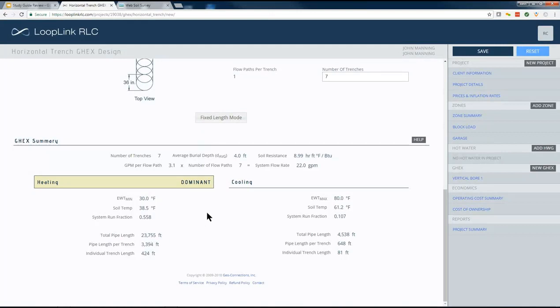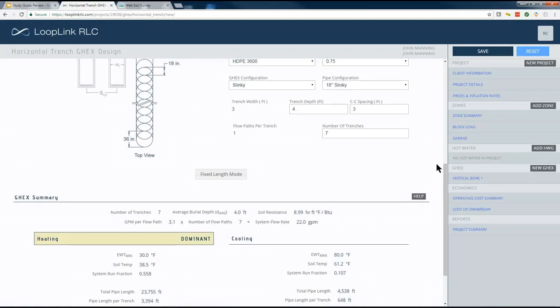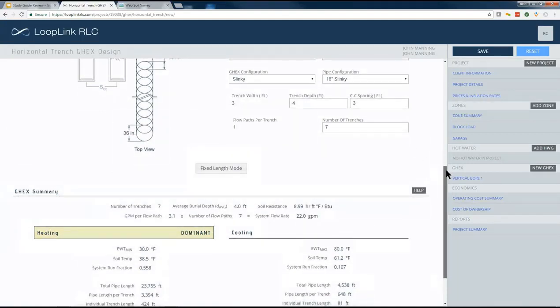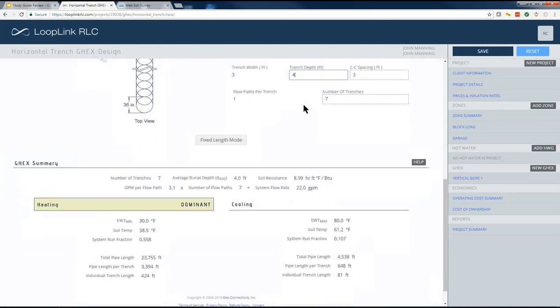Obviously, this is a silly design, but what I want to show you is how a couple of these inputs have a large impact on your calculated lengths. So the first thing we can do, instead of digging a 4-foot trench depth, I want to show you how sensitive the calcs are to the depth overall. The first thing you'll notice is that with a 4-foot depth, our predicted soil temp at that depth at the end of January is 38.5 degrees. We're trying to design for a minimum EWT value of 30. There's not a whole lot of delta T that we're allowing our system there, which is part of the reason why our trench lengths and our pipe lengths are so long here.